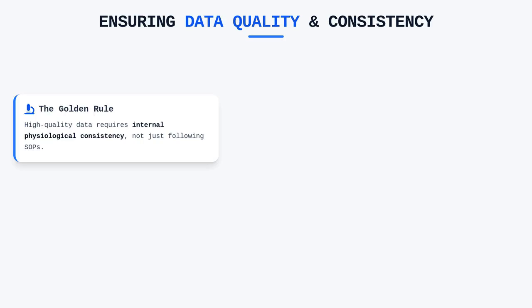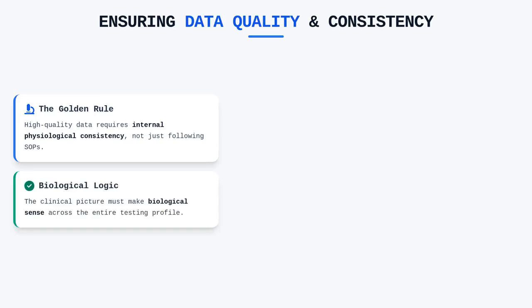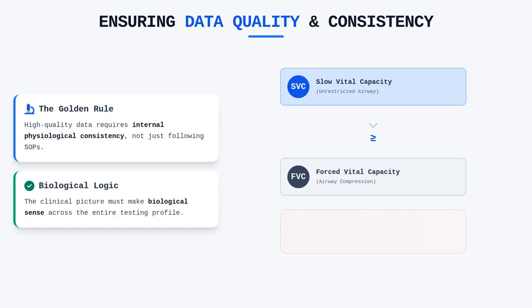Achieving high-quality data requires more than simply following standard operating procedures. It demands a critical eye for internal physiological consistency across the entire testing profile. When a patient performs a slow vital capacity, or SVC, it should generally be greater than or equal to their forced vital capacity, or FVC, because the latter is limited by the physical compression of the airways during a rapid expiratory effort. If you observe an FVC that is significantly higher than the SVC, this is a technical red flag indicating either poor patient effort during the slow maneuver or an inadequate inspiration in the forced maneuver.